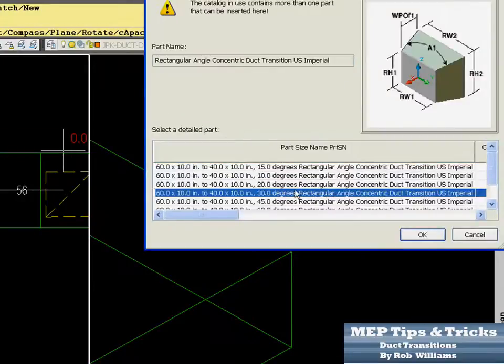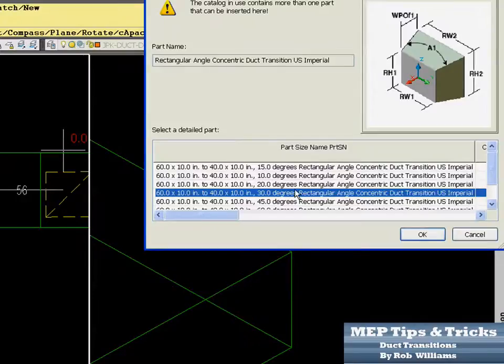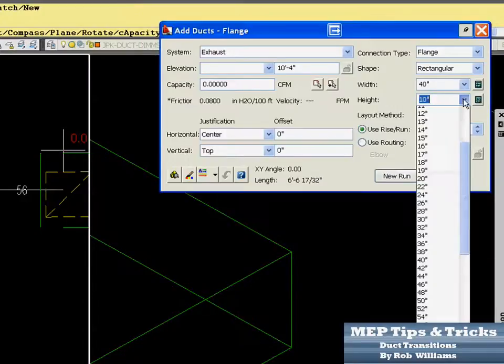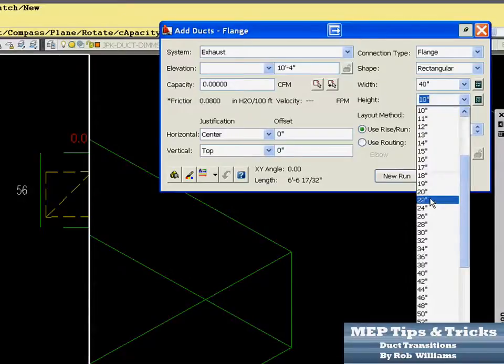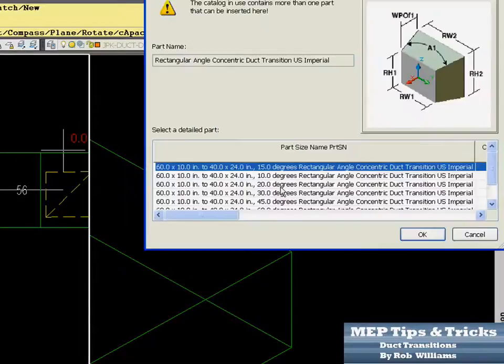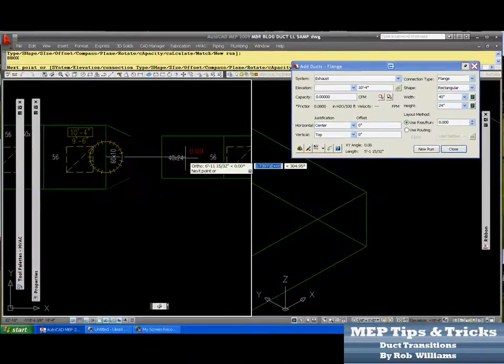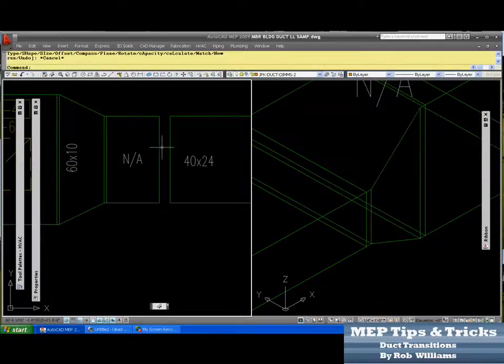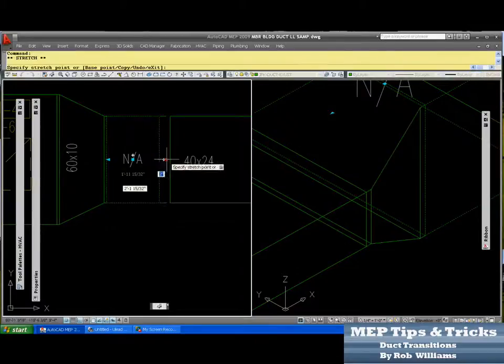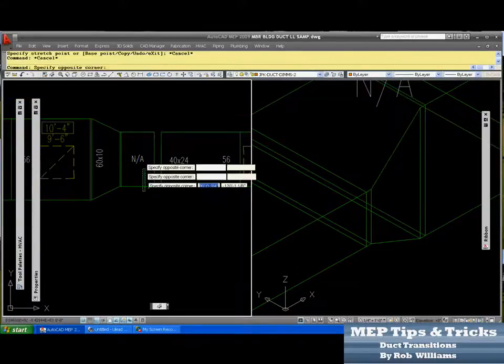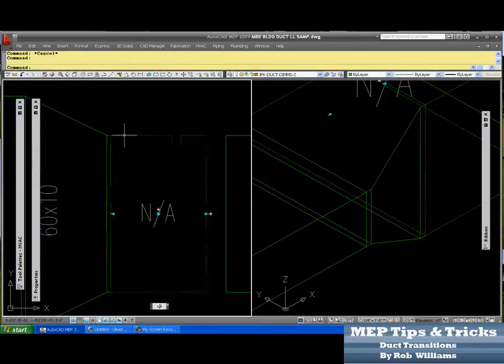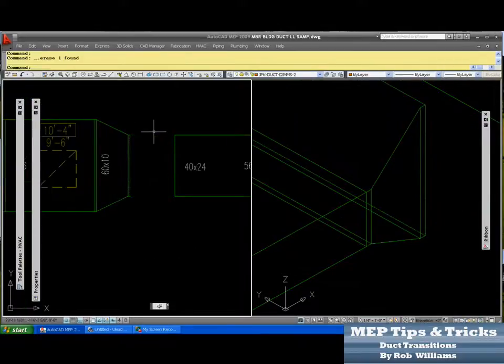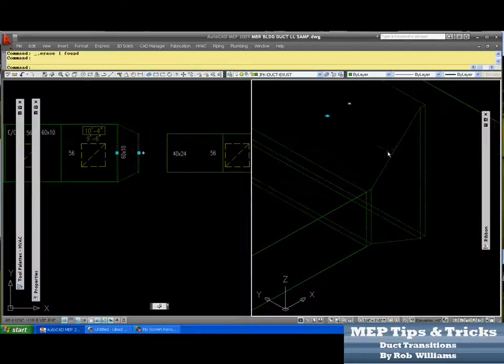I always go 30 degrees, it gives you a good 7 to 1 ratio to start with. It's probably not going to be what you want. And it's going to ask you again once you put the 24 in here, and I'll go to 30. And then I'll just go ahead and draw it, see where I come out at. So now it's going to ask you, say you want to put that little piece of duct in here and I don't want to.